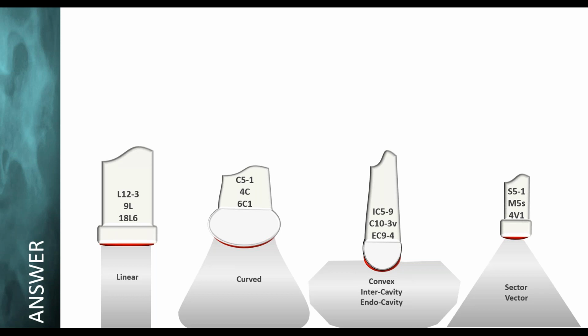And so if we look at all these different probes, this is a Philips probe, this is a GE probe, this is a Siemens probe. The C means curved, it has a curved array. And if you think about a linear array, if you took this array and you bent it, it becomes a curved array. And the advantage is look at this wonderful far field we get, because all these lines fire perpendicular to the face of the probe. And so that's how a curved array is made.